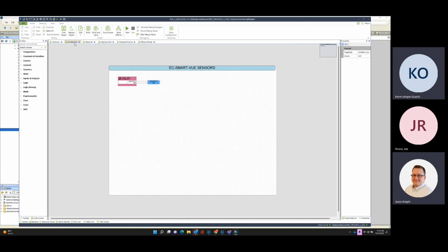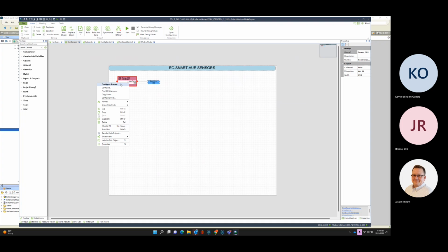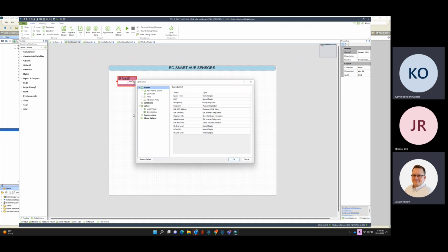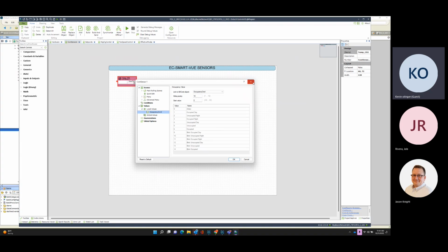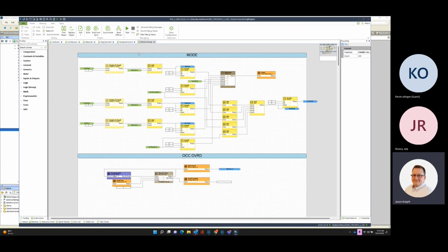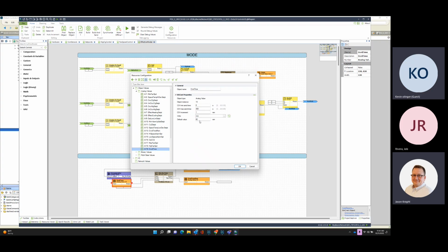And then, so there's logic in here that looks at some local variables for the occupied override. And then it fires this logic down here with your override timer. And right now we have these all at 60 minutes, like we talked about in the meeting.